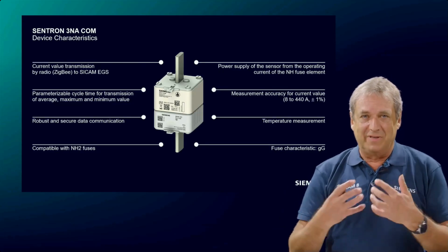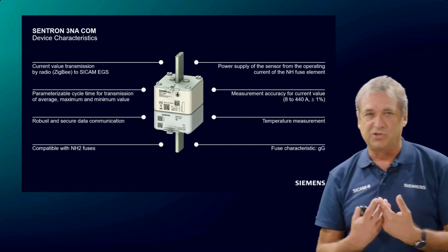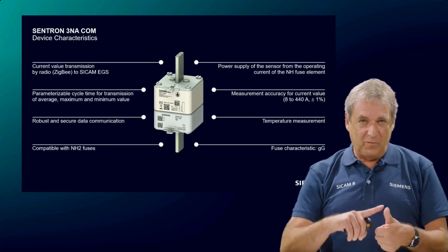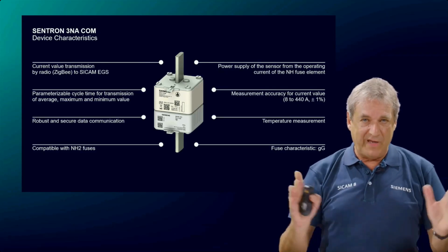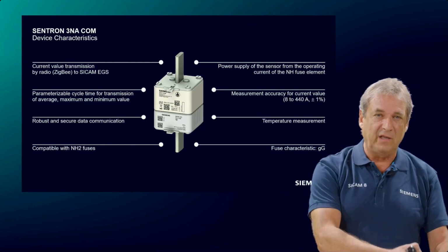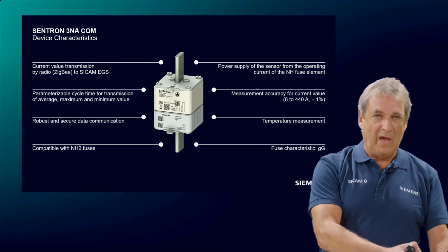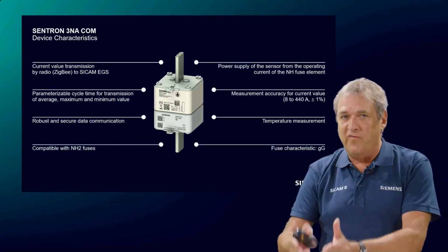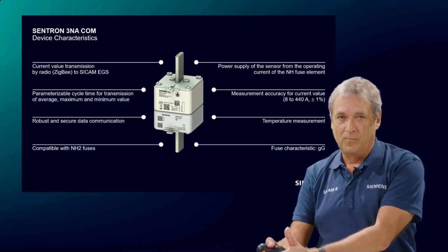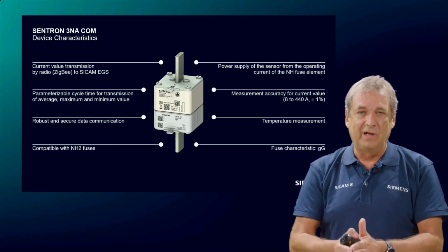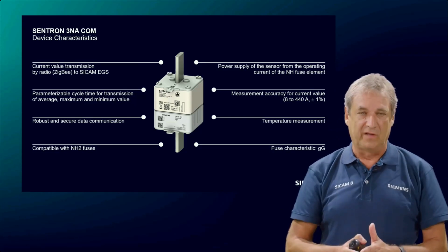What are now really the main advantages of this entire solution? Even without any modification of the existing installation, you get the required information. And the replacement of these fuses can be done within very, very short time. And there is no need for additional cables or any current transformers.